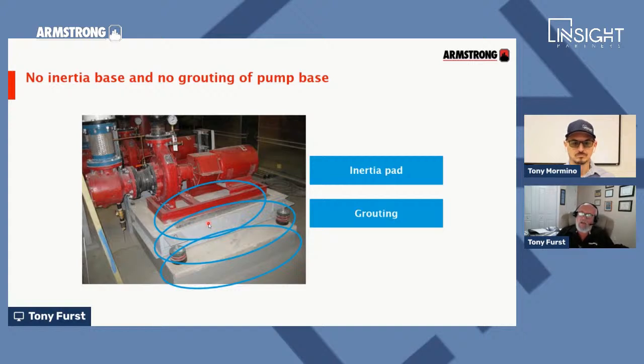The reason you do that is you're adding mass, adding dead weight to the pump to make it vibrate less, to take out the vibration. One of the things we do to take vibration out of a piping system is we add mass to it, we add dead load to it and pull down on it vertically to get it to stiffen up. Well that's what we're doing with the pump, adding mass to absorb any vibrations and give it more weight.